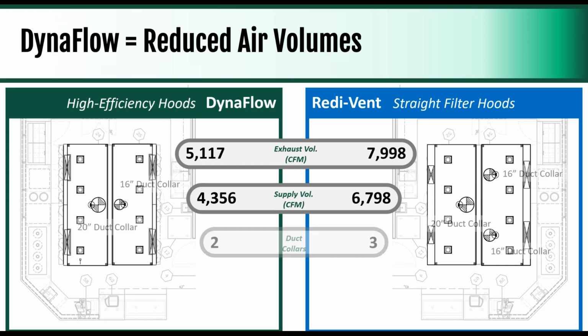corresponds with that. The duct collars, for us, we use the engineered duct on here, and because the version we used was round, we do have a square version as well, but that limits the size you have in the extractor. So on the non-high efficiency hood, we actually had to break this into 2 duct collars. Otherwise, we'd have to use, I think it was a 26-inch duct collar, which wouldn't fit in the extractor, in the grease extractor.